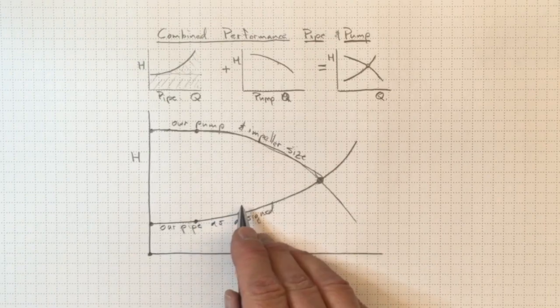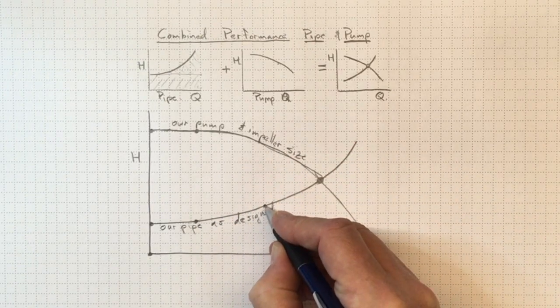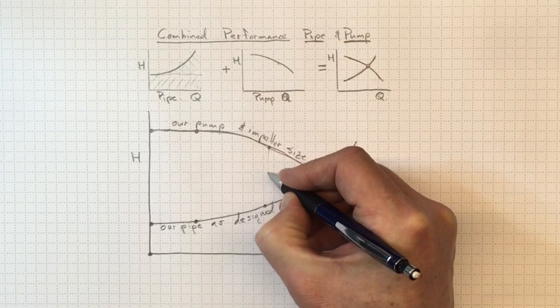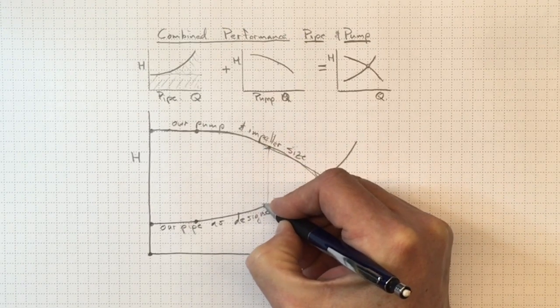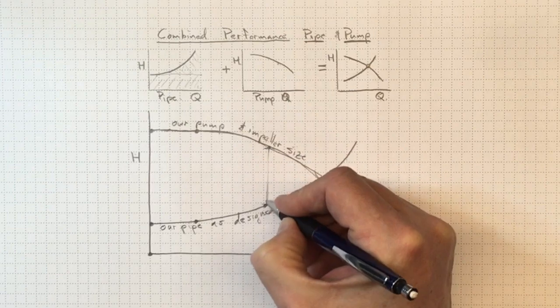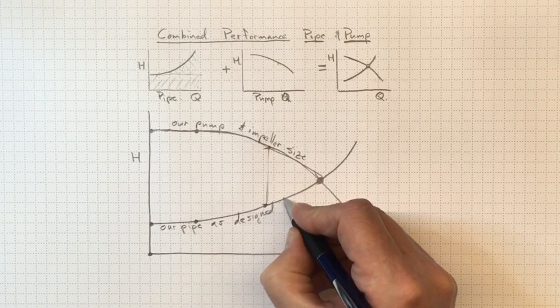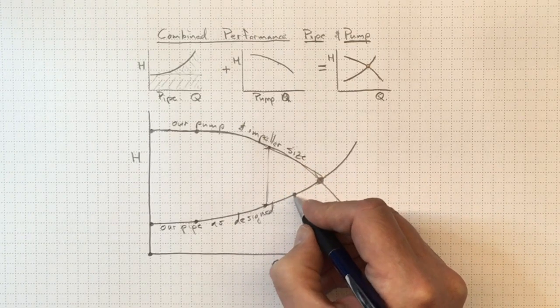So we're going to continue to accelerate that water and it's going to go faster. Now we've got higher losses, so the difference here between what the pump can produce and what the piping system requires is getting smaller. So the force that's accelerating the water in the pipe is smaller. So it's going to move not quite as far in increasing the flow in our next little iteration.